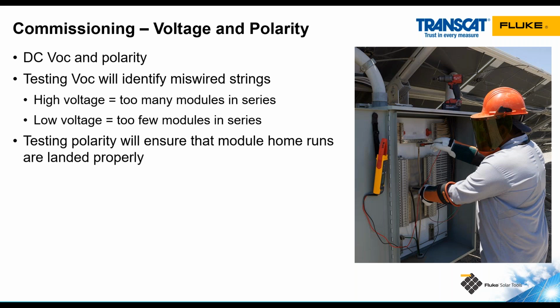Now, testing polarity is to make sure that we connected the positive connectors together and the negative conductors together. If we reverse polarity, we can create a closed circuit where current is flowing through the circuit, and that could cause damage and is a safety hazard. In this picture here, we have someone testing polarity in a combiner box. At the top here, we've got our negative conductors, which come in to this bus bar, and then we've got all of our positive conductors, which come in through fuse holders and then are connected with this large bus bar in the middle there.